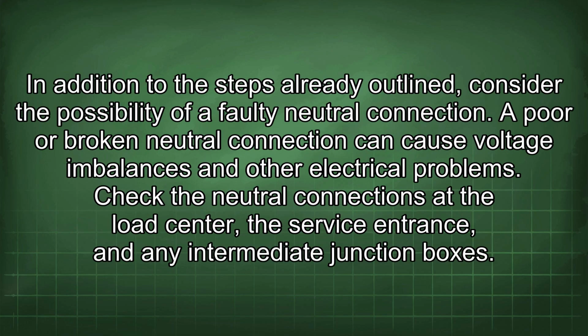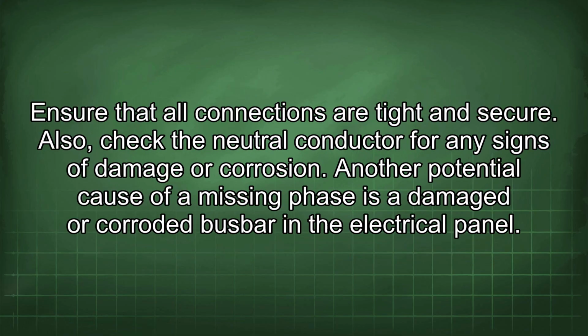In addition to the steps already outlined, consider the possibility of a faulty neutral connection. A poor or broken neutral connection can cause voltage imbalances and other electrical problems. Check the neutral connections at the load center, the service entrance, and any intermediate junction boxes. Ensure that all connections are tight and secure. Also, check the neutral conductor for any signs of damage or corrosion.